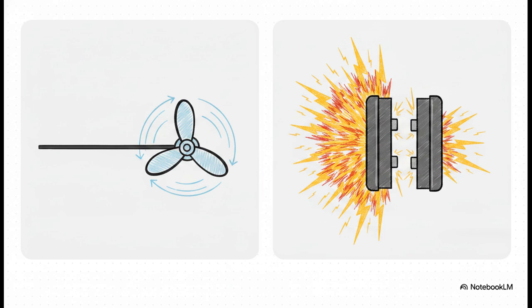But then, look at the second scenario. That is the terrifying extreme. When a catastrophic short circuit hits, that exact same breaker has to instantly, on command, switch off the absolute worst-case fault the network can possibly throw at it. It literally cannot fail, it can't weld shut, and it definitely cannot hesitate. Because if it gets this wrong, well, nothing downstream survives.